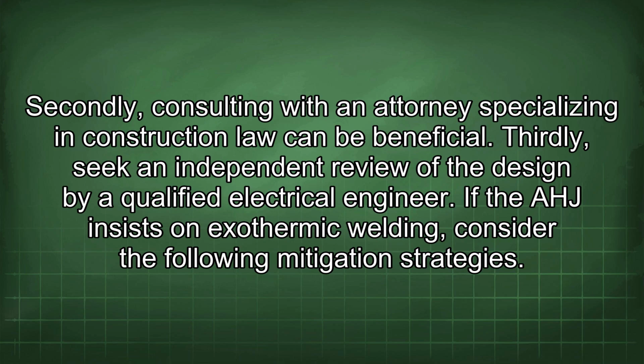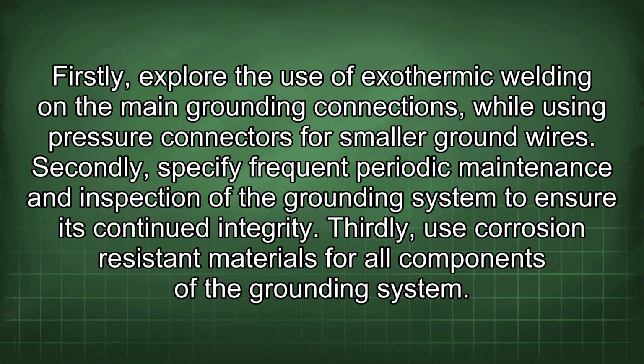If the AHJ insists on exothermic welding, consider the following mitigation strategies. Firstly, explore the use of exothermic welding on the main grounding connections while using pressure connectors for smaller ground wires. Secondly, specify frequent periodic maintenance and inspection of the grounding system to ensure its continued integrity. Thirdly, use corrosion-resistant materials for all components of the grounding system.